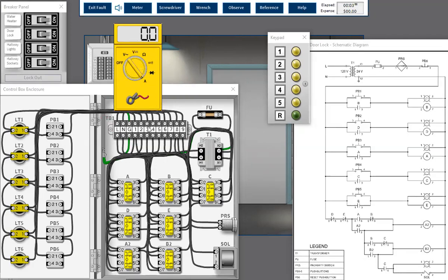Tell you what, let's check current. Let's check it right here. And we hit 1.15. It doesn't seem too bad. Three, let's get 2 coils on. 4, 1 coil. 3, 1. So quite possibly it's a bad connection, a loose connection. So let's go ahead and lock it out.